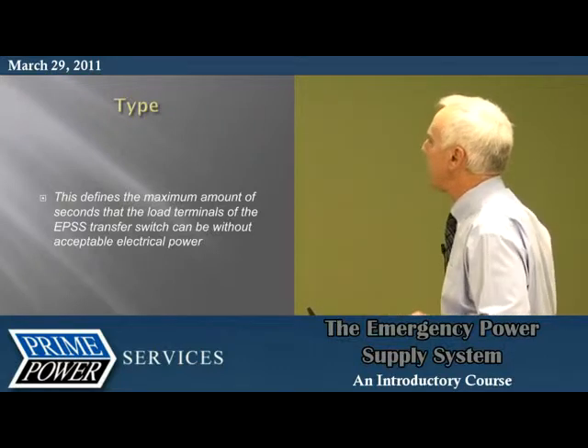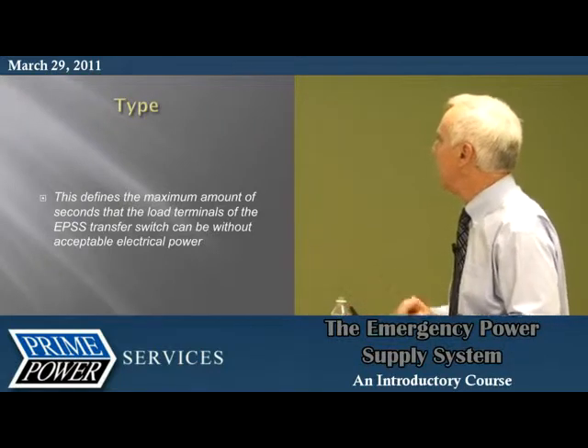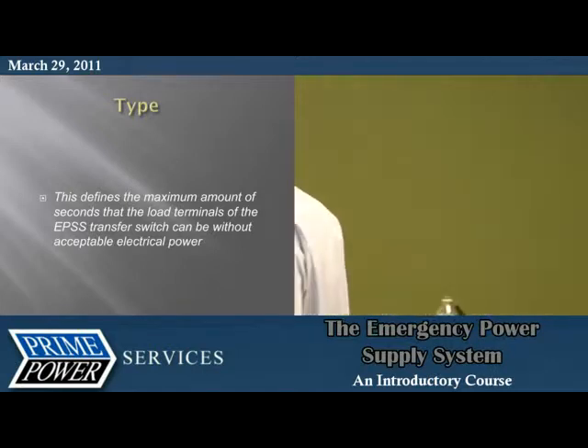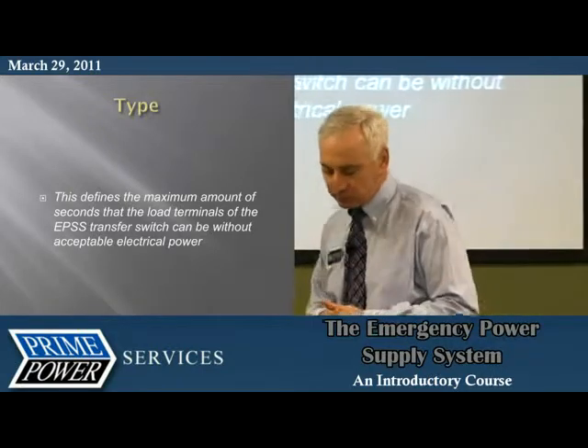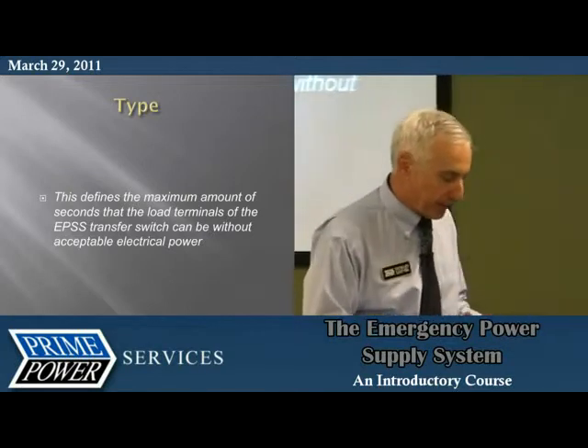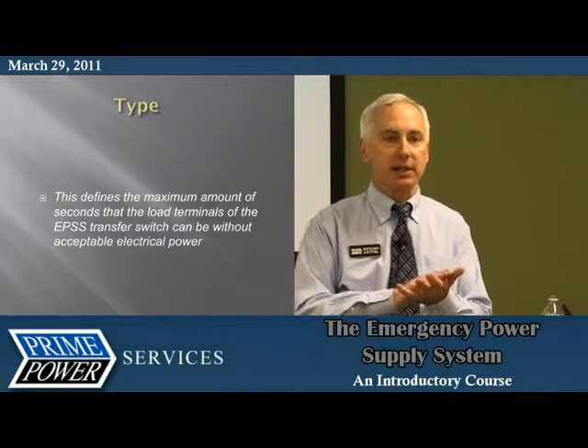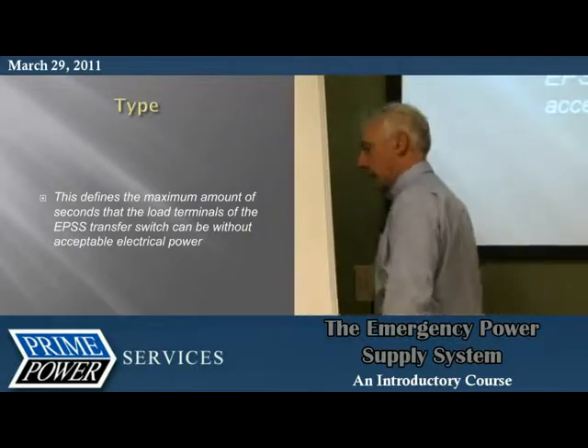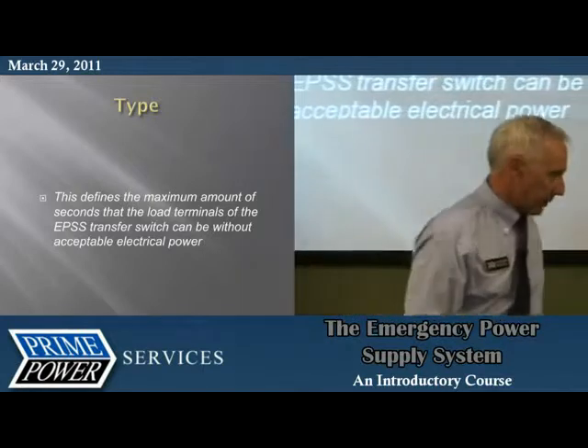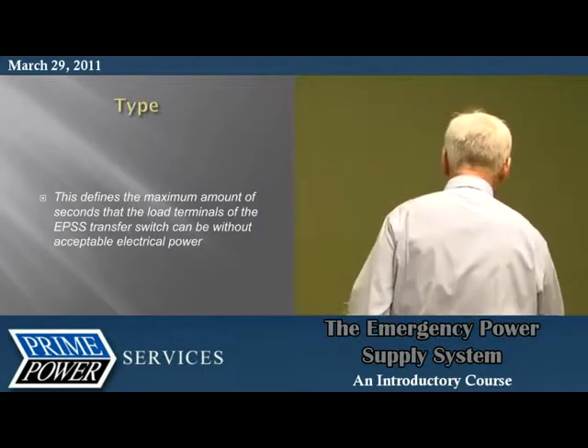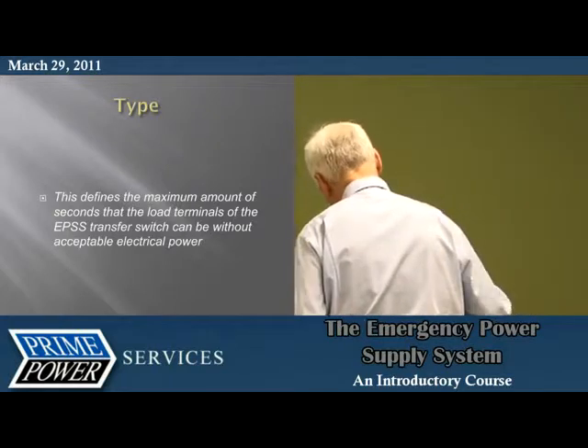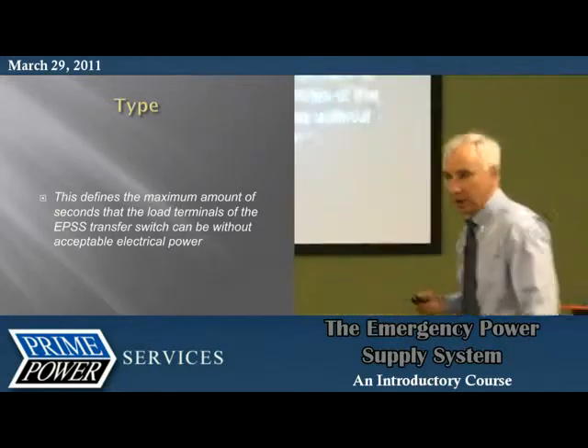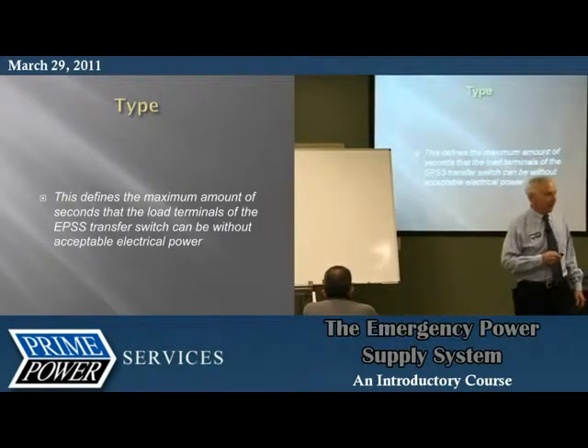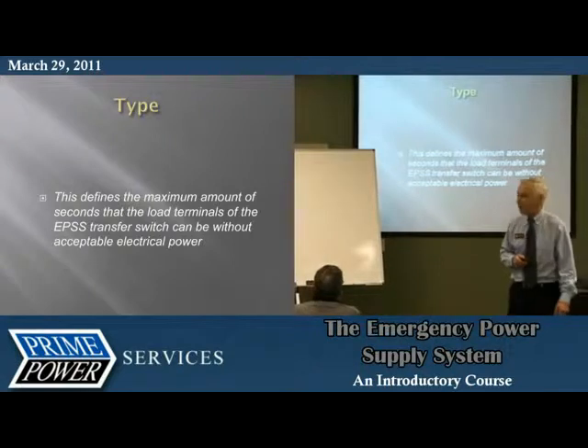The type defines the maximum amount of time that the load terminals of the transfer switch can be without acceptable electrical power. This is the one that really gets us, because in our world that's 10 seconds. So from this little light over here, above this transfer switch, which is being fed by this transfer switch, from the time it goes off to the time it comes back on, it's got to be less than 10 seconds.